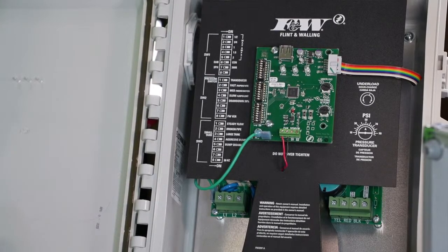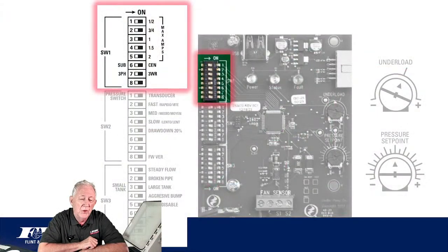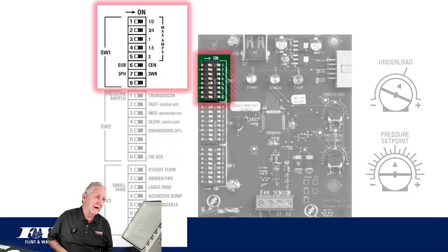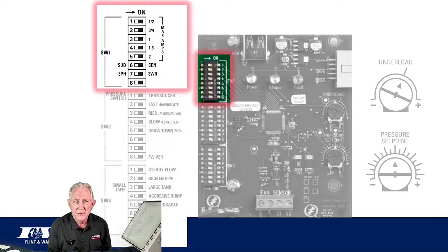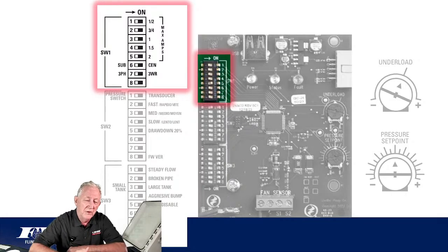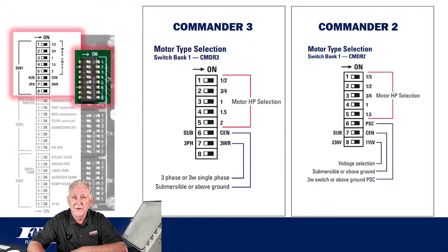Just below that, position 6 into position 7, and this is again only specific to 3-wire motors and the Commander 3 itself. It's your difference between just a standard 3-wire single-phase motor, or are we running a 3-wire 3-phase motor? So again, it's just a matter of moving the switches to the proper position so that the drive knows what type of motor, what horsepower, what phase we're going to be operating in. All right, so that's the bank up there at the top.